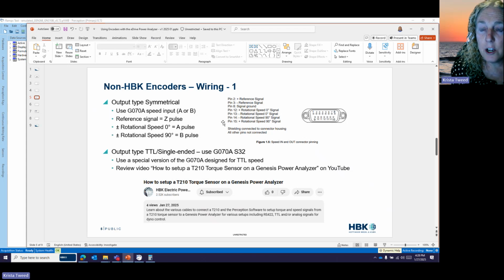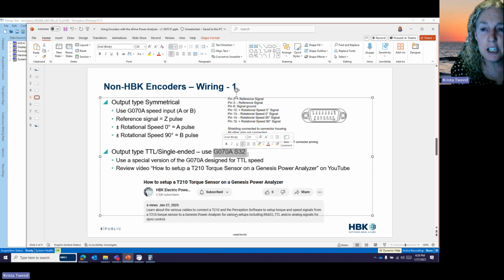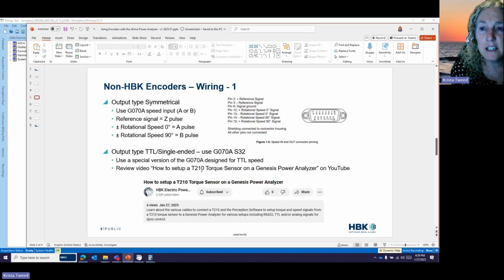Now, if you have an encoder that has a single-ended or TTL type output, you have a couple different options. The first option is if you don't have any need for a standard G70A, you can purchase a G70A S32, which is a special version of the G70A designed for sensors that have a TTL speed output. And there's already a nice video on our YouTube channel about how to set up a T210 torque sensor with a Genesis power analyzer. The T210 torque sensor also has a TTL speed. So just search that YouTube channel for that title, and you'll find a lot of information that Mike already put together on how to connect that type of input.